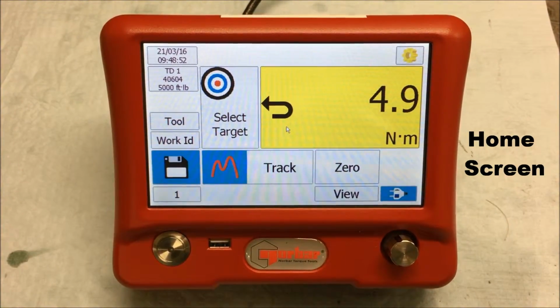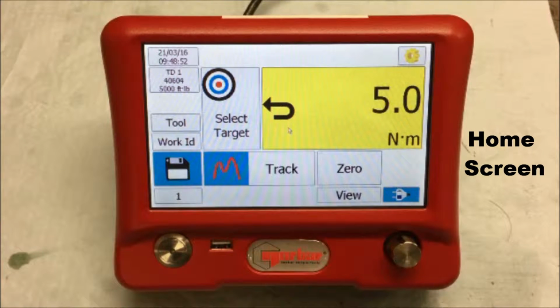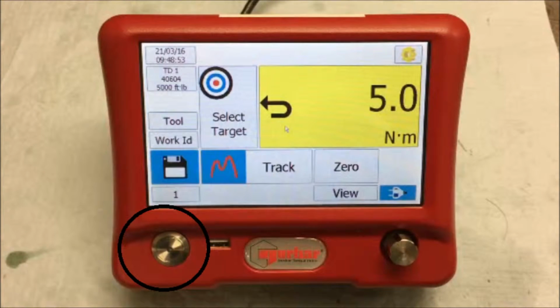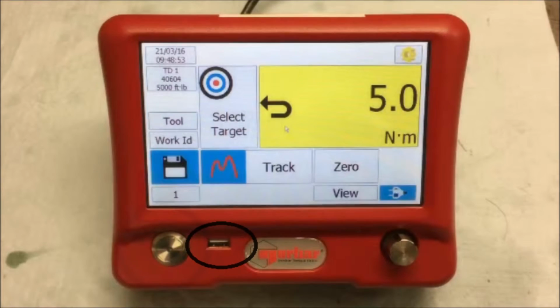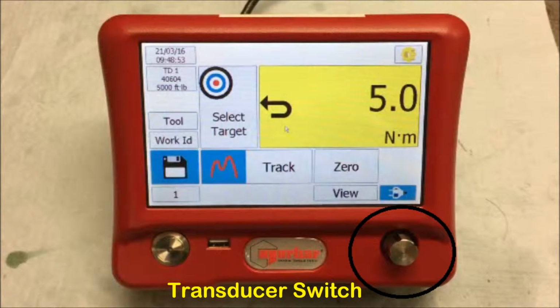Once the T-Box is started, you will be taken immediately to the home screen from where most of the testing and calibration work is undertaken. You'll notice at the bottom of the T-Box the first button, which wakes it up from standby mode, a USB port for importing and exporting data and records, and on the right hand side a 4-button switch to allow the operator to switch between any of the 4 transducer ports on the rear of the T-Box.